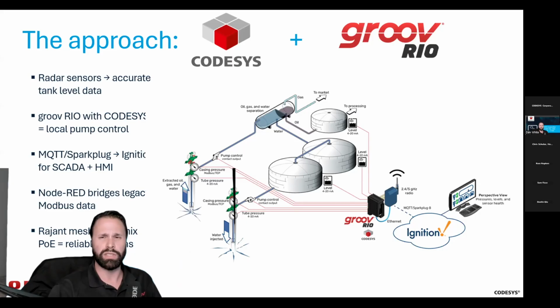They also used a little bit of Node-RED on their groov RIOs to facilitate communications with older serial-based Modbus devices. The Rio supports a USB to serial converter that communicates RS-485 and RS-232—in their case, 485—to these Modbus RTU devices. That way they didn't have to tear out existing pressure transmitters and older gear. They could use the older gear still out there, and it could all be part of the same data stream and data ecosystem.